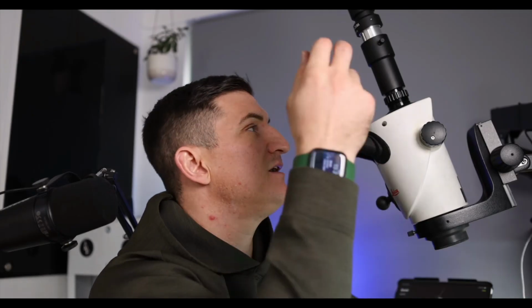So this comes in 3 versions: the no camera, an integrated camera, and the version with the port on the top. The integrated camera is now 4 or 5 years old. It never had a very good image when it came out. It obviously hasn't improved since, and it can't be changed out or upgraded in the future. So I would just rule that out entirely. You want the one, this is the S9D, which has the port for the camera, and then you can put on whatever camera you choose. That's what I would go for.